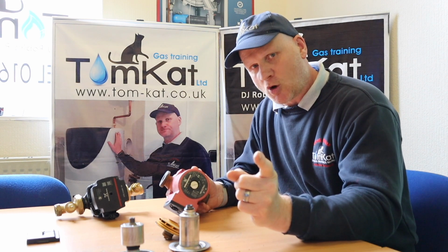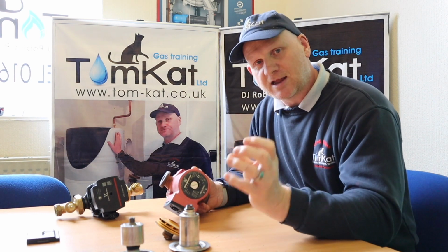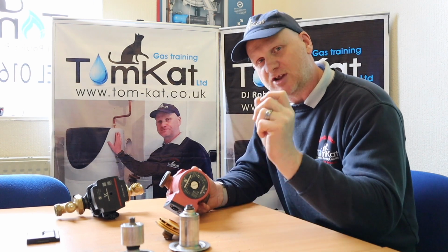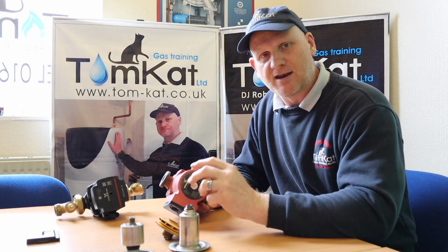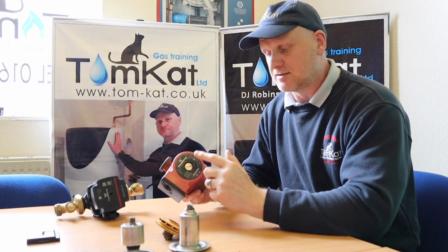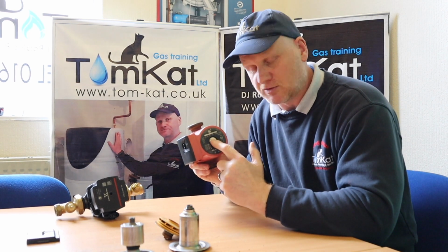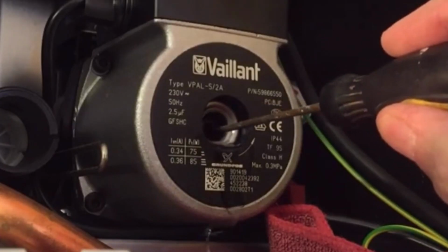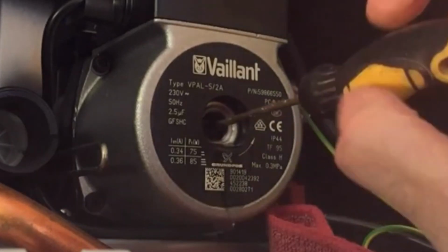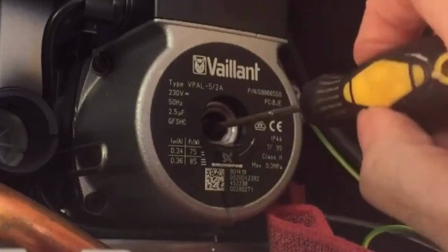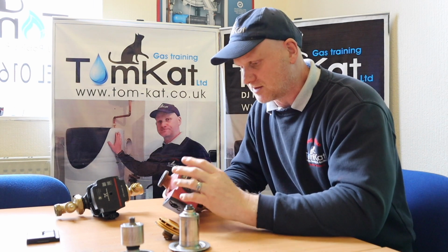If it starts up again, then it was just the pump stuck, but if it doesn't start up again, then the capacitor's gone. And freeing the pump is through this little screw hole here. You get a screwdriver, turn it left and right, and it'll free it off. Because in the summer months when you're not using your central heating, this is not in a combi, this is on a traditional system. In the summer months, if you're not using your boiler for heating, what can happen is the pump can stick. So that's one thing.